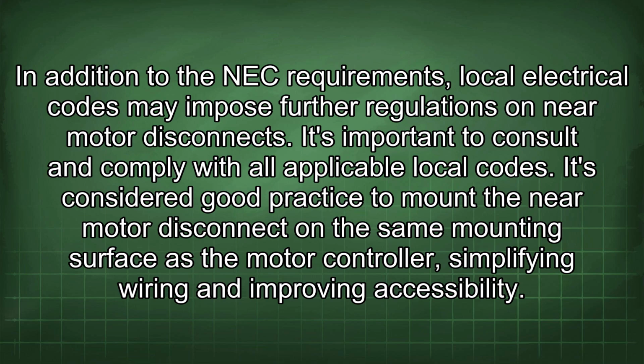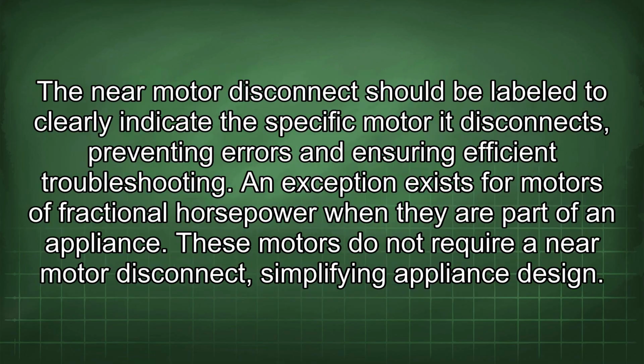It's considered good practice to mount the near motor disconnect on the same mounting surface as the motor controller, simplifying wiring and improving accessibility. The near motor disconnect should be labeled to clearly indicate the specific motor it disconnects, preventing errors and ensuring efficient troubleshooting. An exception exists for motors of fractional horsepower when they are part of an appliance. These motors do not require a near motor disconnect, simplifying appliance design.